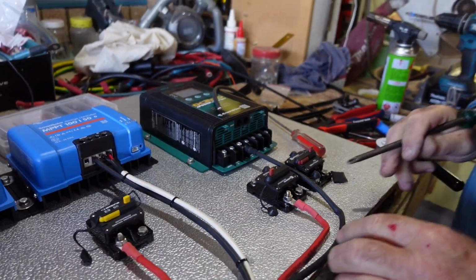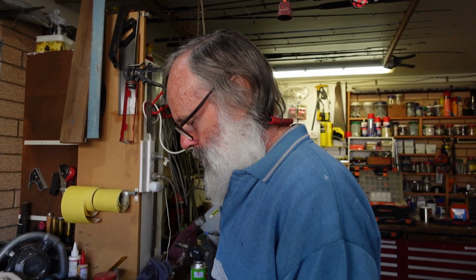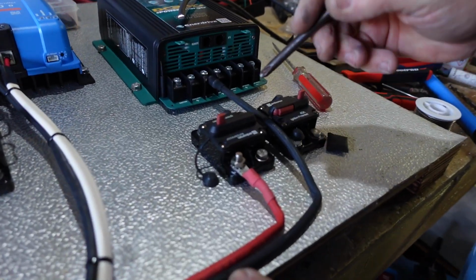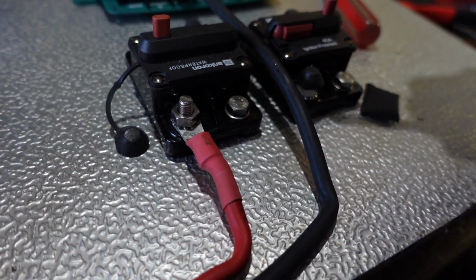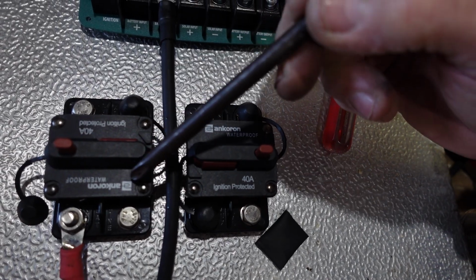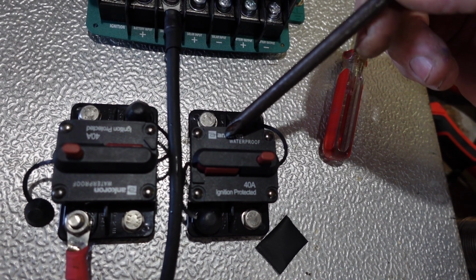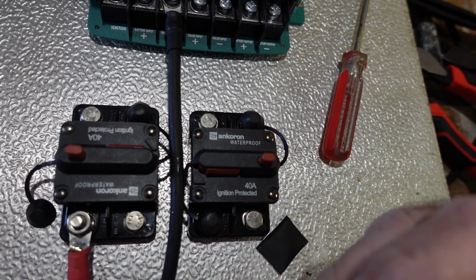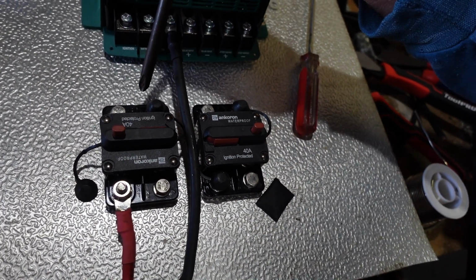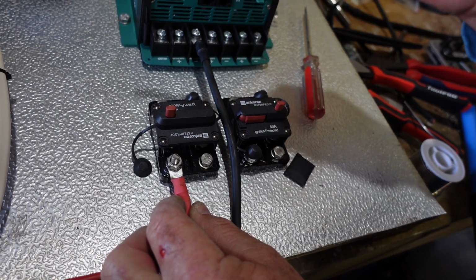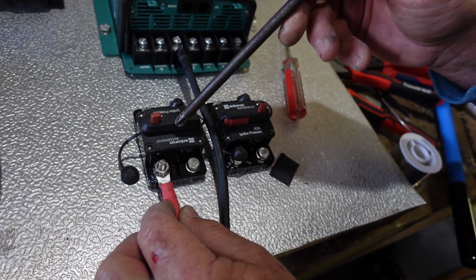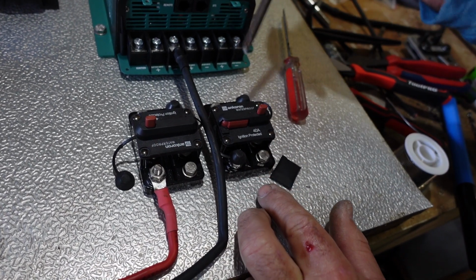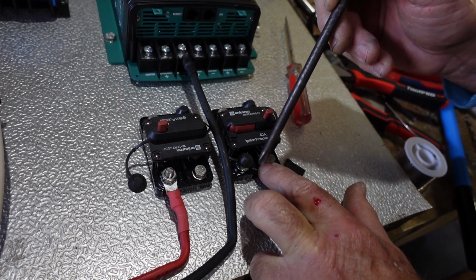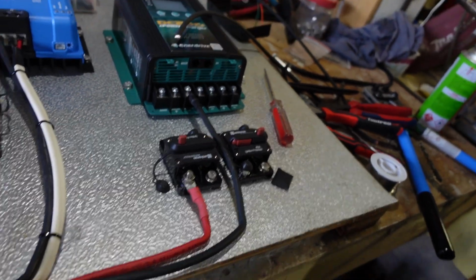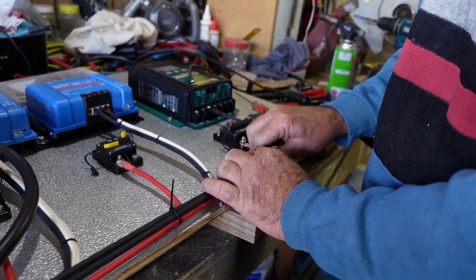Another thing you might want to watch is these circuit breakers. If you buy this type, they're actually marked battery and load, written there in very fine print. Keep in mind this one is actually upside down compared to that one - I haven't mounted them upside down, I've mounted them according to the way the current flows. So they're labelled battery and load, think of it as this end's got to go to the battery. The simplest way of thinking about it is that's going to the battery and that's feeding out, and this one is actually feeding back into the battery. So this is your battery, and although that's going to the battery, it's actually auxiliary. A bit back to front, but they are position sensitive apparently.